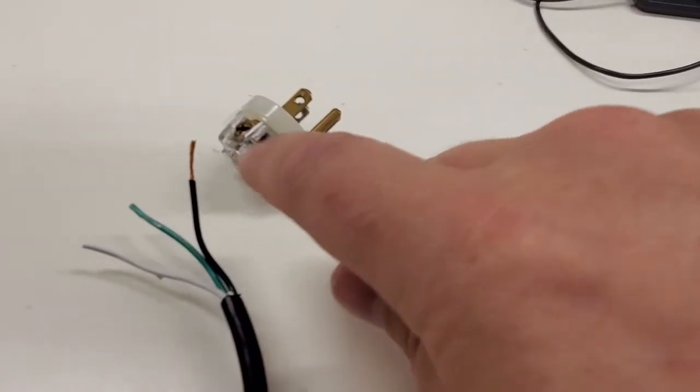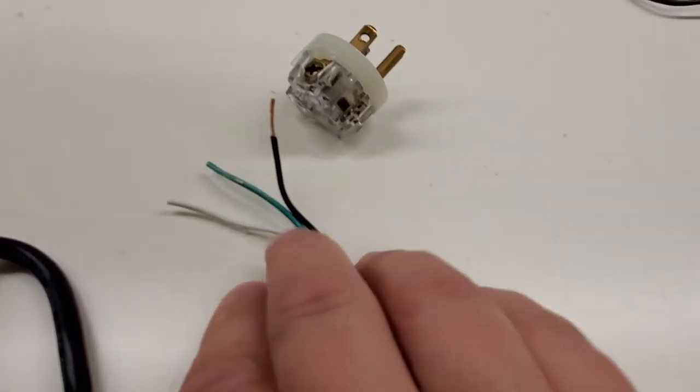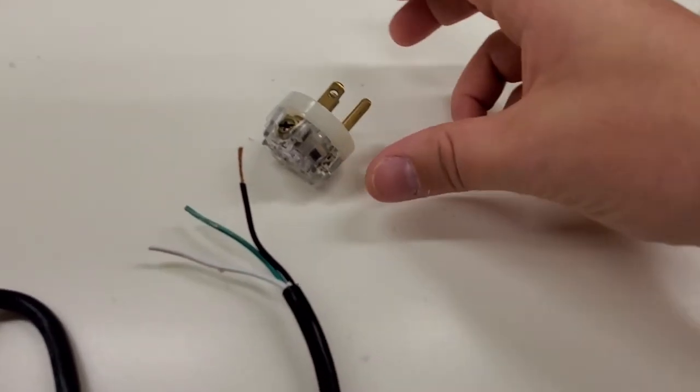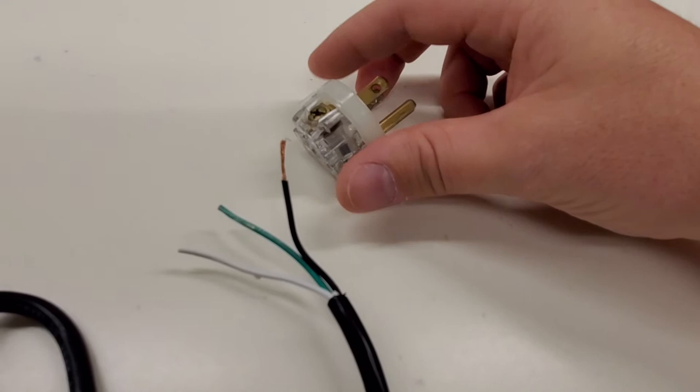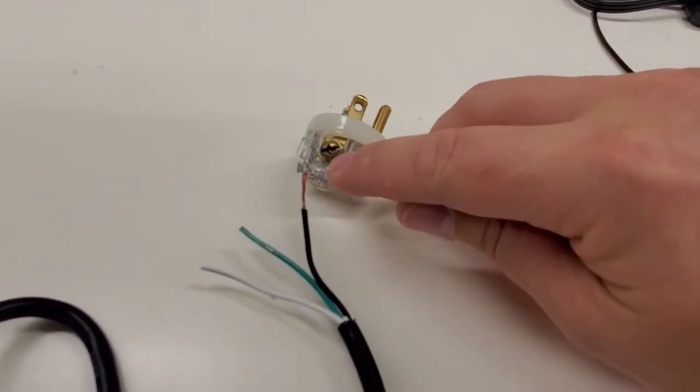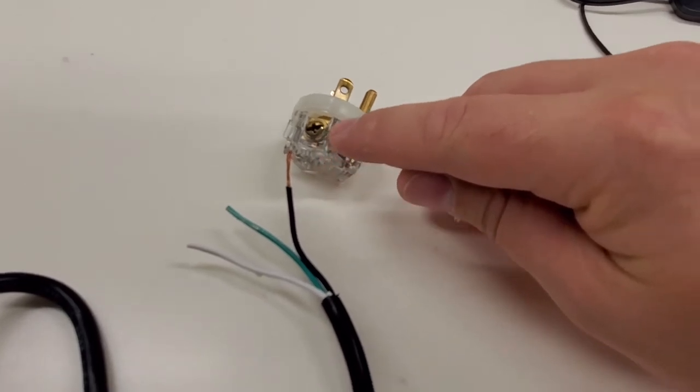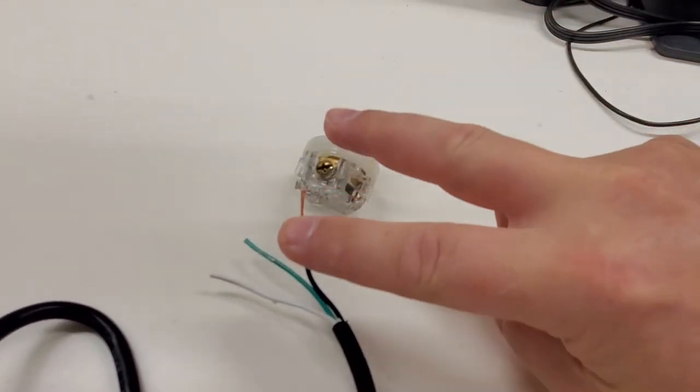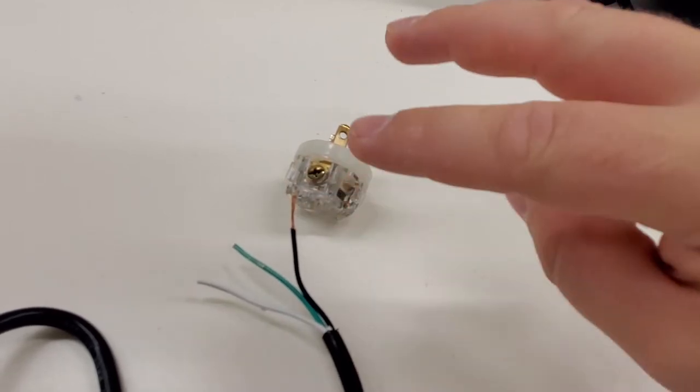And the reason that thermal expansion matters is because not only does your hot wire get warm under load because of amps that are going through it and the natural resistance of the wire, but also this terminal right here is going to get warm. And you want those both to expand and contract at about the same rate, pretty close to it.